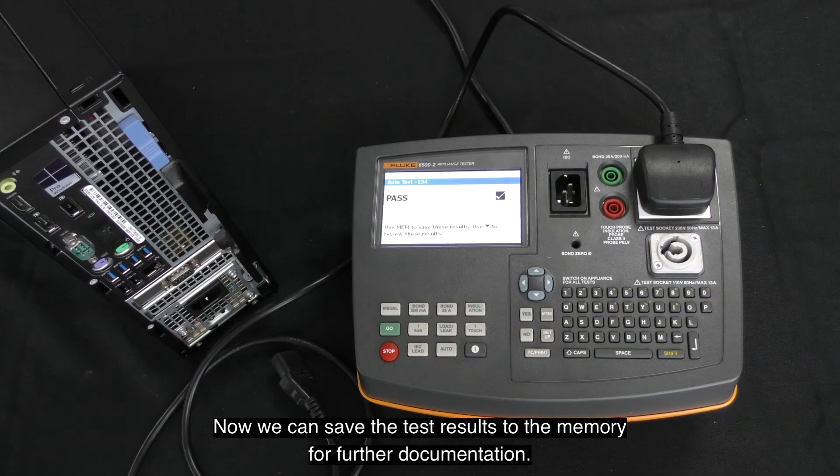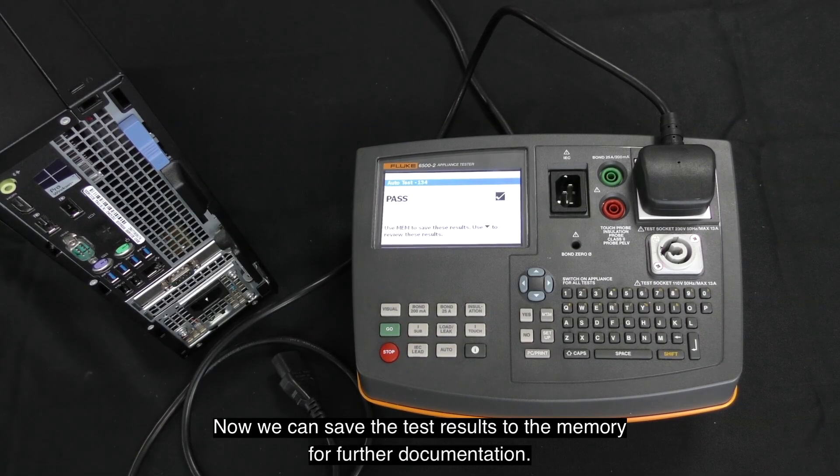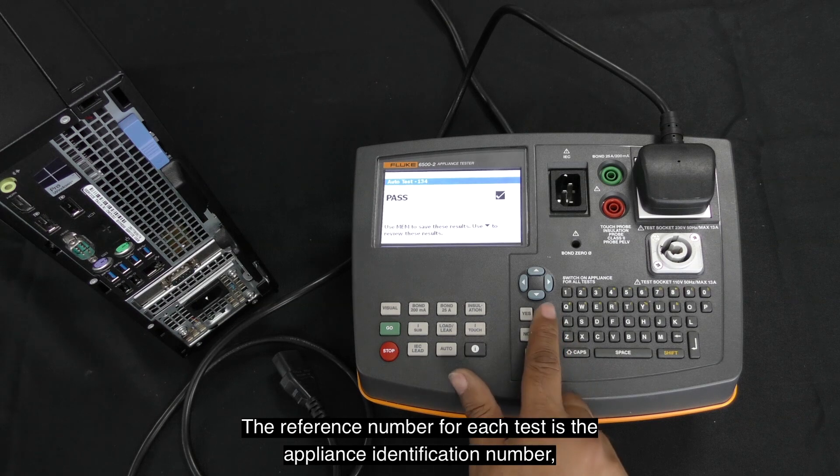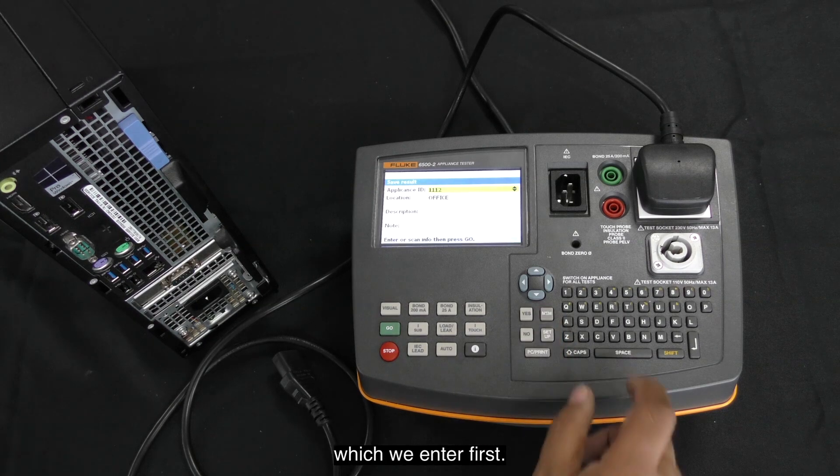We can save the test results to the memory for further documentation. You can enter the data by using the internal keyboard. The reference number for each test is the appliance identification number, which we enter first.